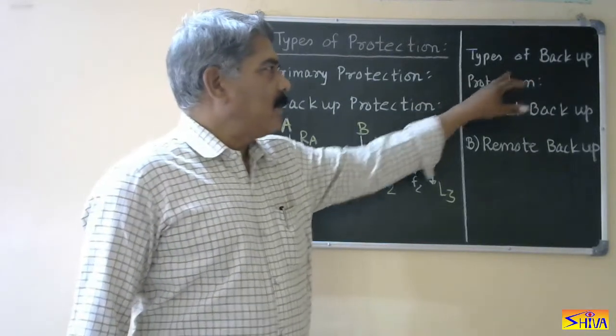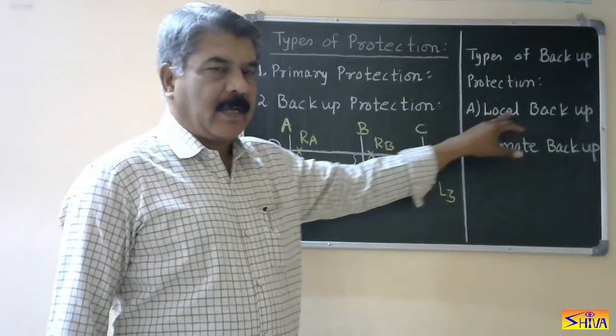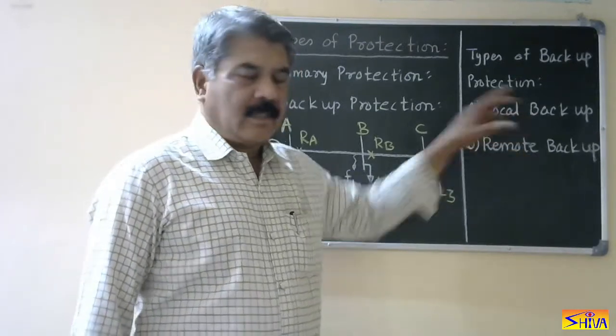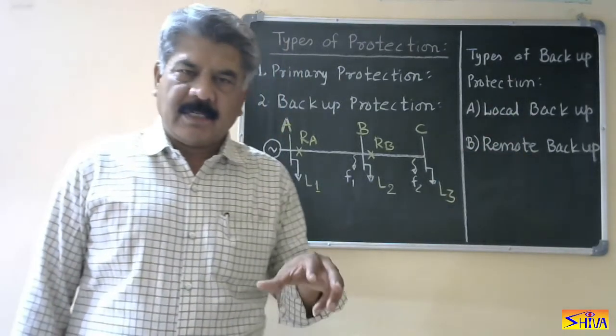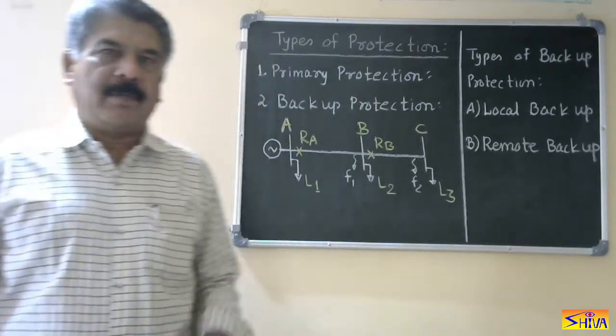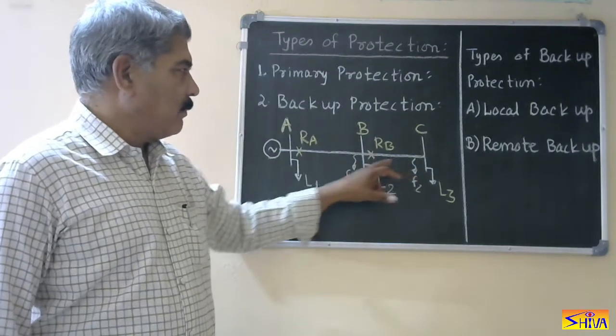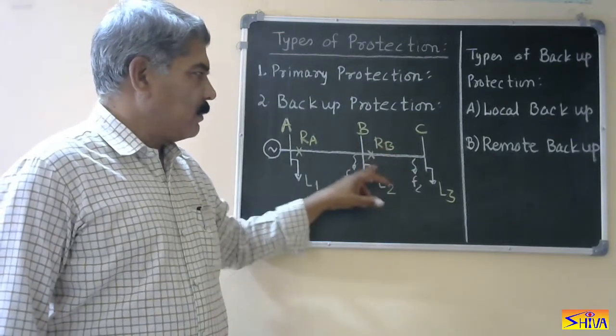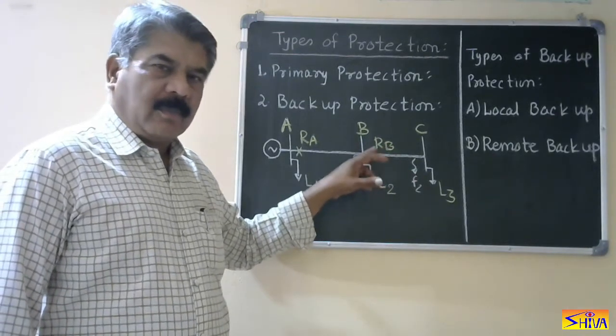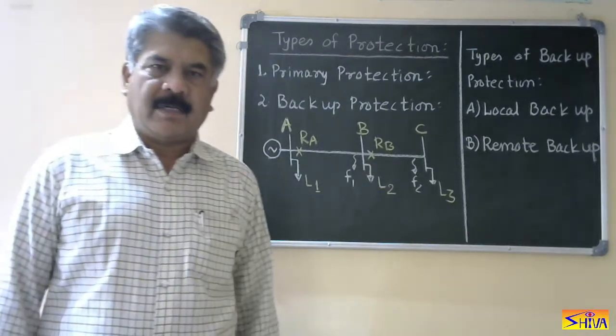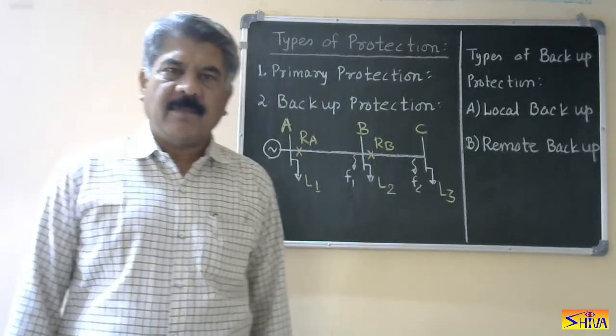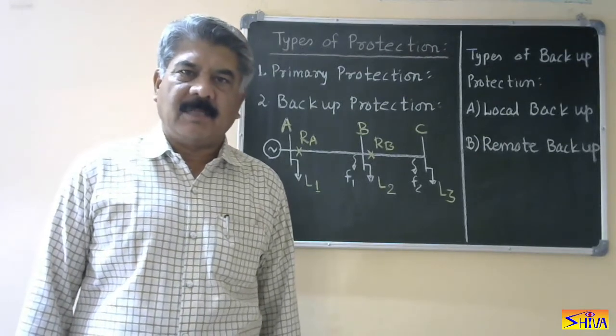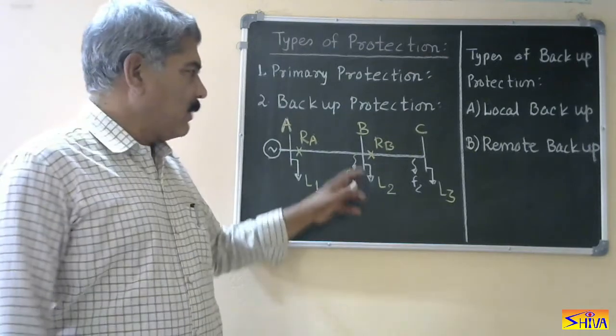Now let us see the types of backup protection. There are two types: one is local backup, and the second is remote backup. Local backup means it is provided at the same place where the primary protection is located. It can be provided by a duplicating principle — either using two different relays or two different circuit breakers, or duplicating the entire protection system at that point.